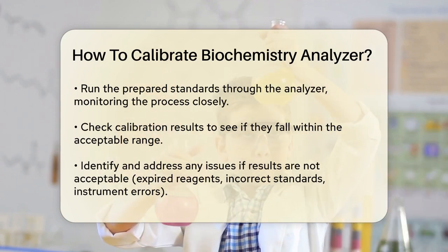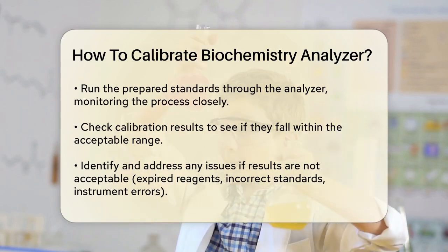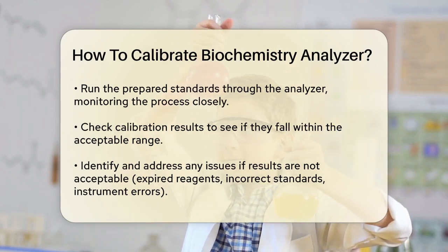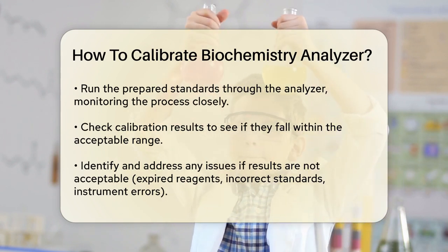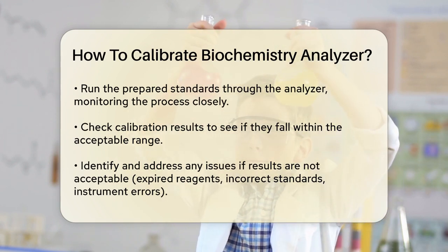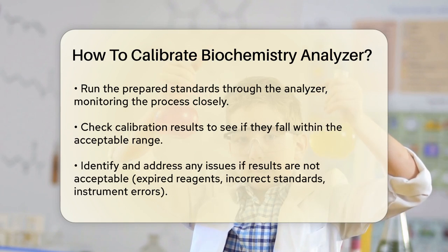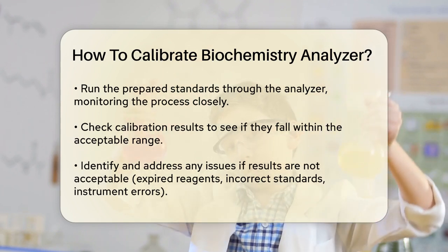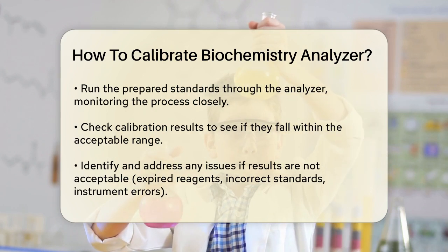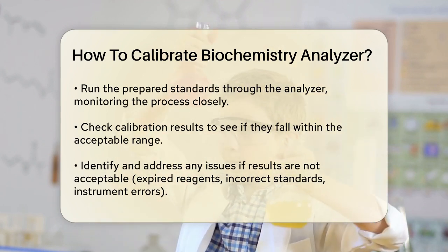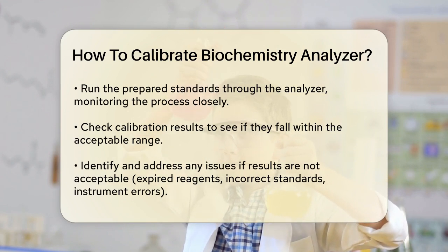If the results are not within this range, you need to identify and address any potential issues such as expired reagents, incorrect standards, or instrument errors. If everything looks good, the next step is to run quality control (QC) samples. These samples act as a secondary check to ensure the analyzer is providing accurate and reliable results, verifying that the calibration was successful and that the system is functioning correctly.